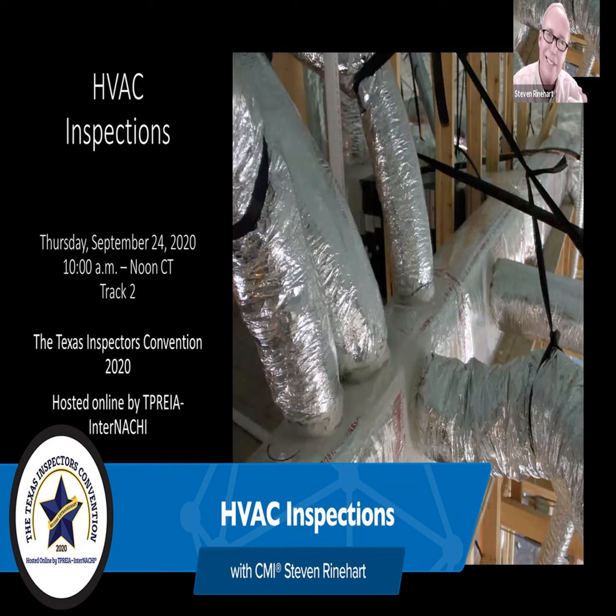Combustion, dilution air: if it's inside, especially inside the house, I want some combustion air ducts. The typical high and low goes up into the attic. I like to have vermin screens over them. They've got to stick up above the depth of the insulation, plus say another foot. And they can be screened at both ends. The idea is just to communicate air.